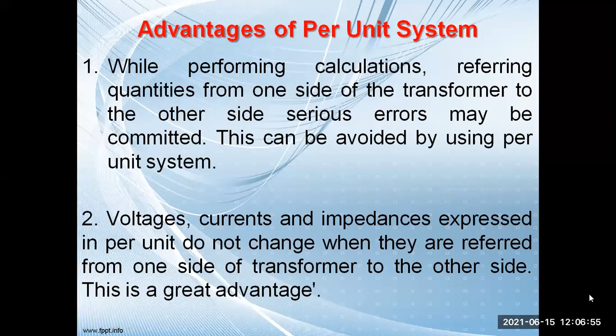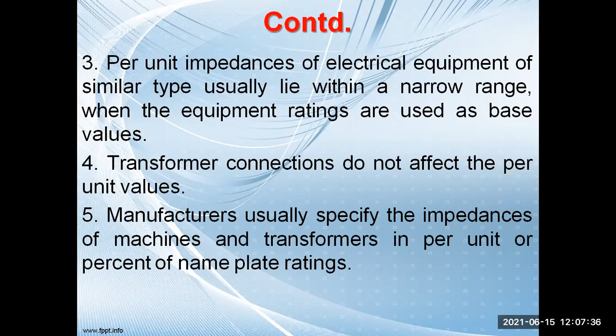The per unit impedance of equipment of similar type usually lies within a narrow range when equipment ratings are used as base values. Transformer connections do not affect the per unit values — that is the main thing. Manufacturers usually specify the impedances of machines and transformers in per unit or percentage of nameplate ratings, since they also prefer this per unit system and normally specify data either way on the nameplate.